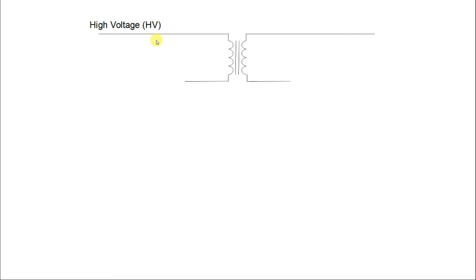Our secondary side here is our low voltage side - it's 600 volts or less, so it's considered low voltage. I've denoted here that we're stepping down 12,470 volts to 480 volts.